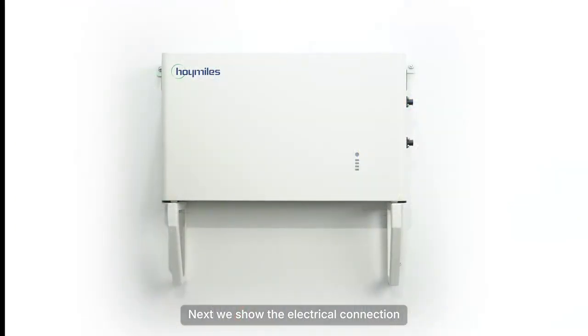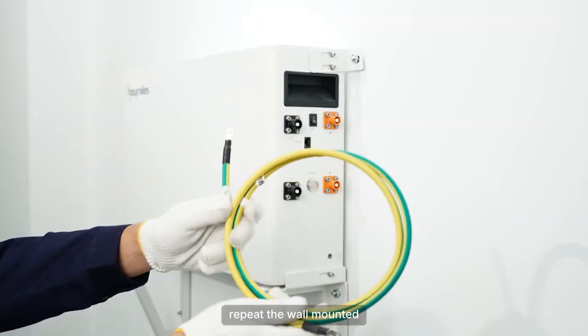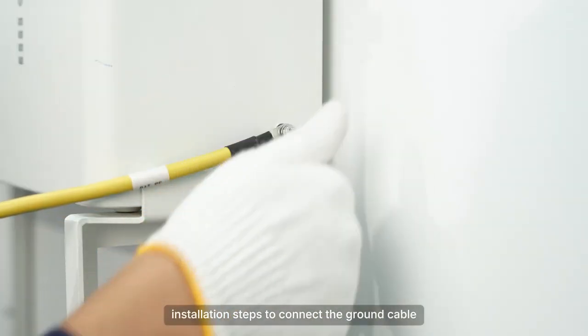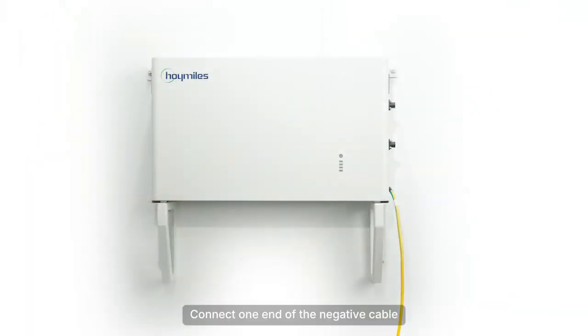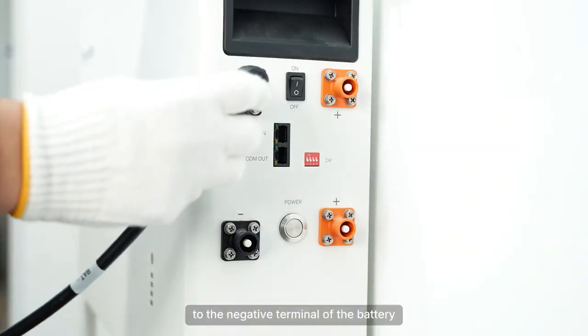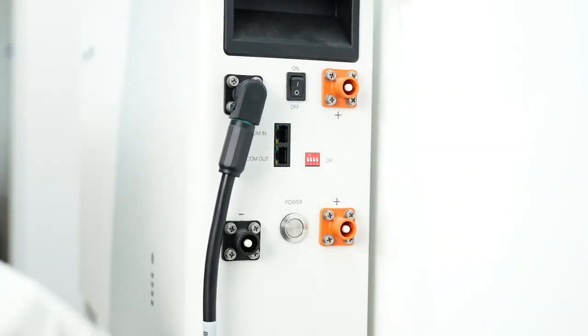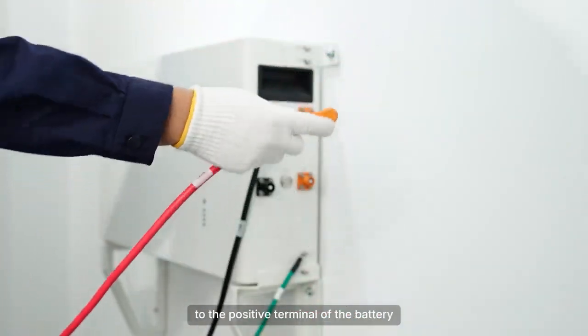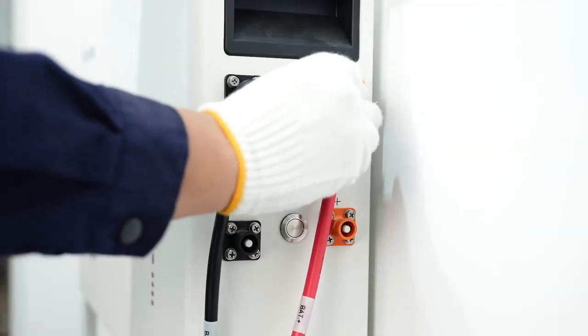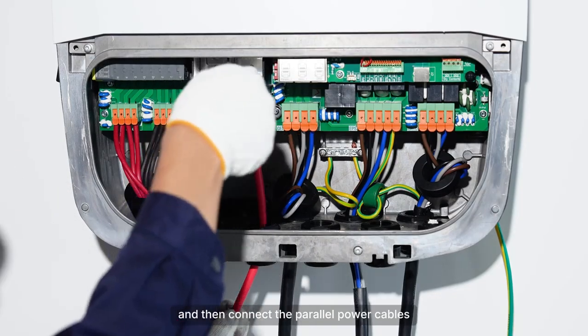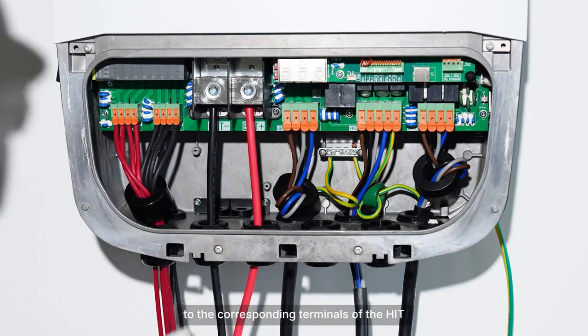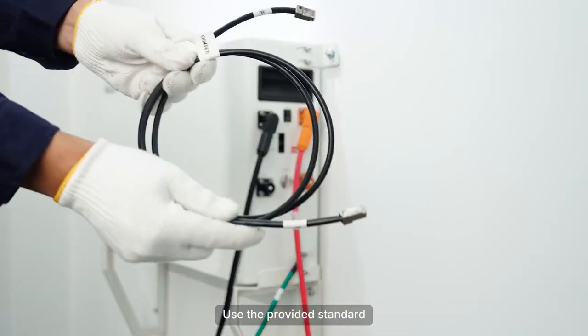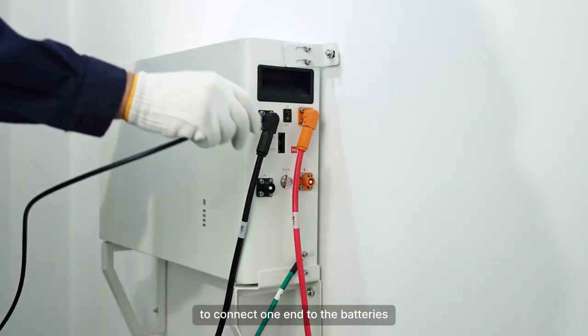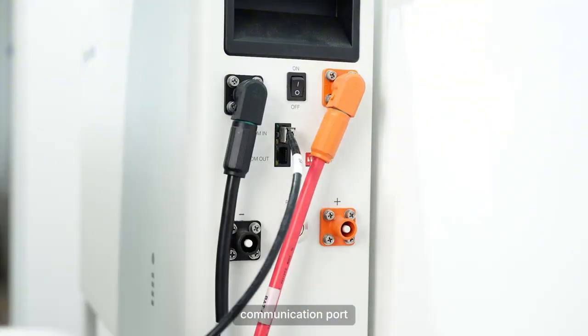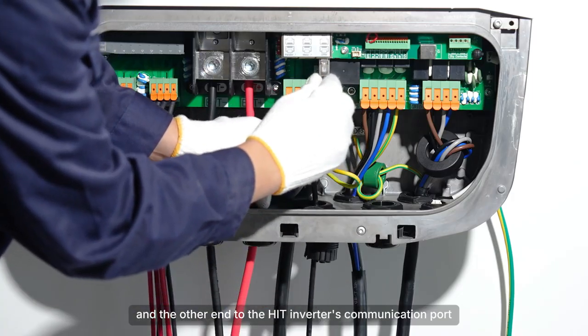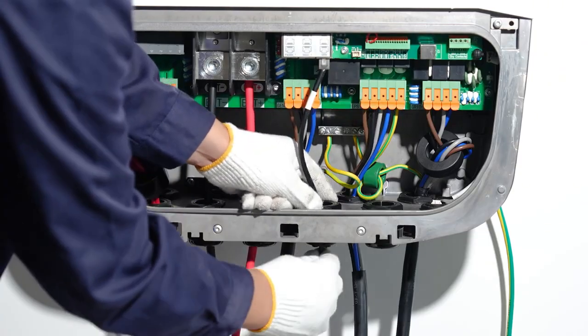Next, we show the electrical connection for wall mounting installation. Repeat the wall-mounted installation steps to connect the ground cable. Connect one end of the negative cable to the negative terminal of the battery, and one end of the positive cable to the positive terminal of the battery, and then connect the parallel power cables to the corresponding terminals of the HIT. Use the provided standard Ethernet communication cable to connect one end to the battery's communication port and the other end to the HIT inverter's communication port.